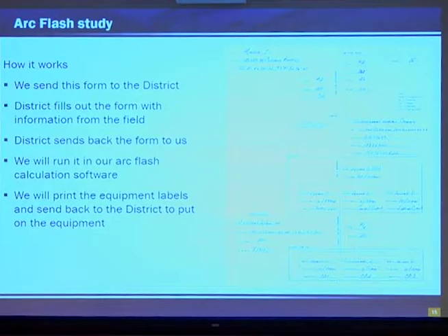Thank you. So currently TRF, we're doing a pilot where we're sending this form to districts to fill out the site information from the field, such as conductor sizes and breaker information. Then the districts send the information back to us, and we'll run our ArcFlash calculation software. And ultimately, like Michael said, we want to print out equipment labels and send them to the districts so they could put them on their equipment. The equipment label is going to show the incident energy at different buses and the PPE category to wear when servicing that particular electrical equipment.